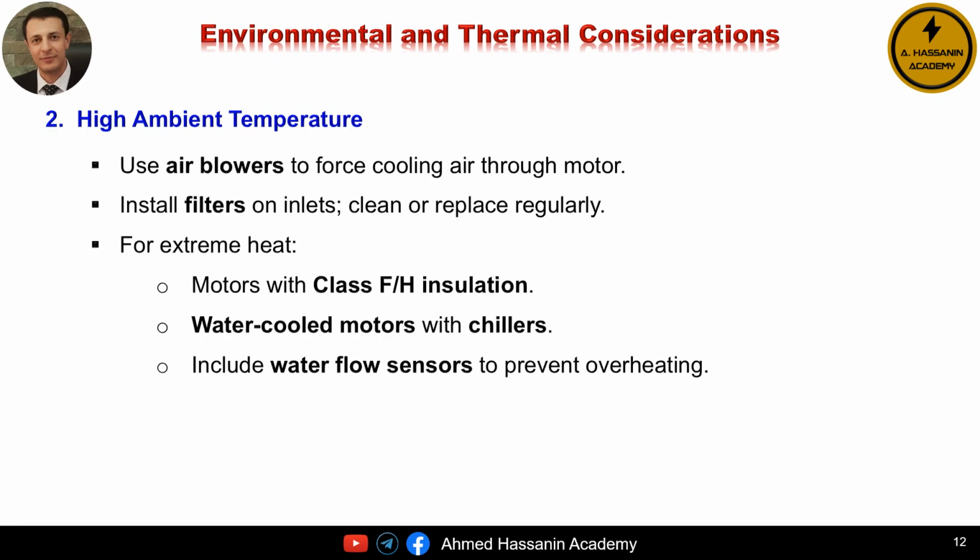Now, in really extreme heat, we have to take more serious measures. One option is to use motors with high thermal class insulation, like class F or H, which can tolerate higher temperatures without damage. Another option is water-cooled induction motors, where water flows through a cooling system connected to external chillers to remove heat. And here's an important safety point.